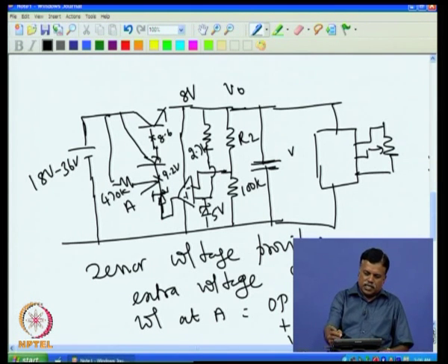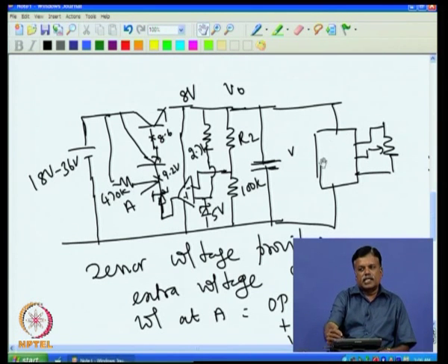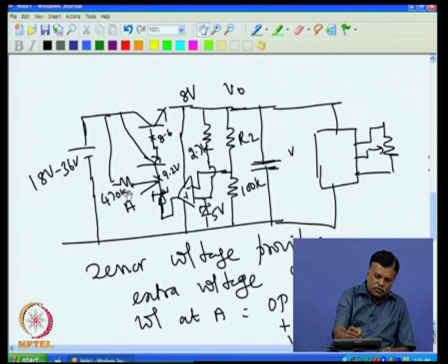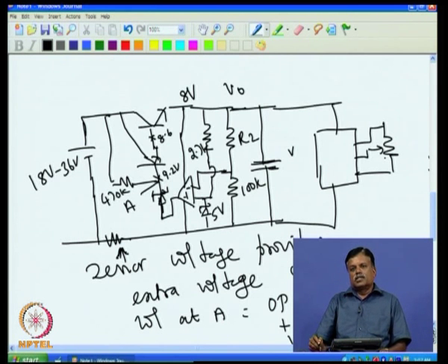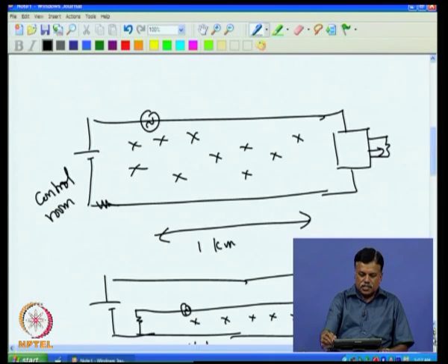Now, we can go ahead and see how to design the next part, that is this current transmitter part, because the current that is flowing here returns here and that comes here. In actual use, they will be using one resistance here and measure the current, and that current should give the position information corresponding to this potentiometer. So, we have to design it now. Since the voltage across this is now constant, this receives a constant voltage. Now this current transmitter can be designed easily. Let us see how to design this current transmitter.